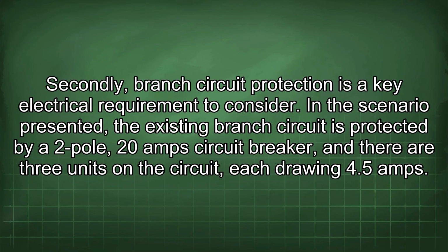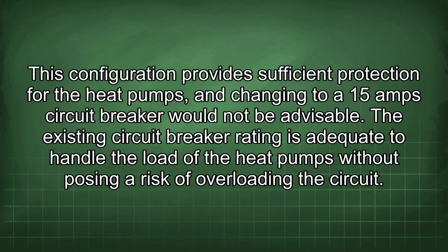Secondly, branch circuit protection is a key electrical requirement to consider. In the scenario presented, the existing branch circuit is protected by a 2-pole 20 amp circuit breaker, and there are 3 units on the circuit, each drawing 4.5 amps. This configuration provides sufficient protection for the heat pumps, and changing to a 15 amp circuit breaker would not be advisable.